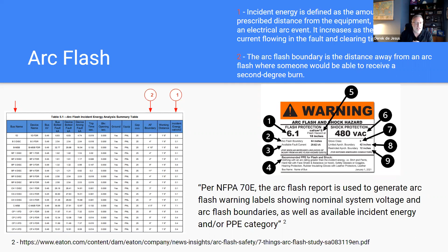Okay, I'm going to jump back over to this one here. Yeah, and it's just as important when you're looking at mechanical equipment and doing your testing that you verify you're not going to have nuisance trips when you're testing. You're going to be increasing the load of that circuit when you're testing your devices. You don't want those breakers to constantly trip. So you want to make sure that study has been done, and maybe that's a prerequisite to your functional testing, or it's something on your pre-functional checklist, that the SCCAF study has been submitted, approved, and settings have been applied. That's a great catch-all statement so your team is aware before you go into testing on the mechanical side.